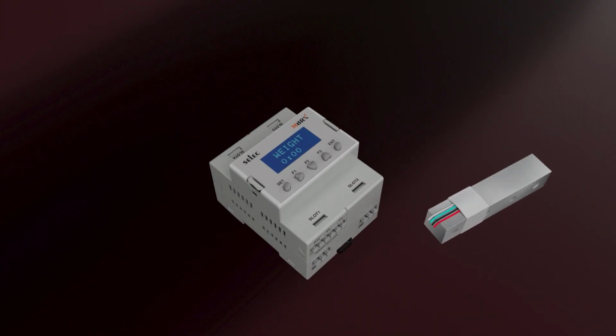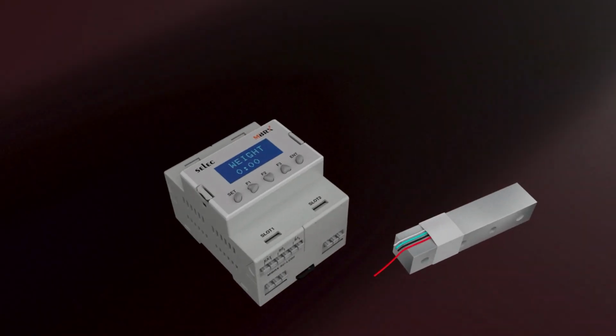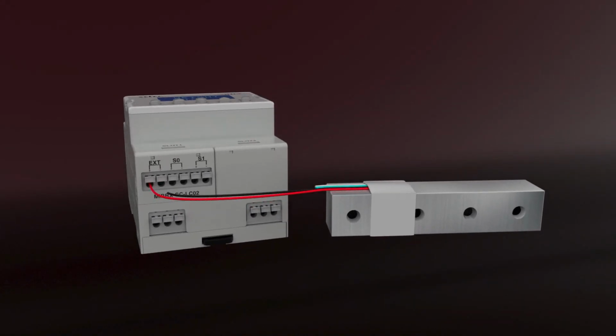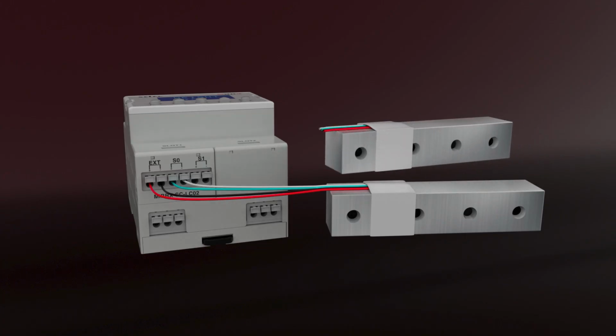The sensor excitation wires are connected to the respective excitation positive and negative terminals, while the sensor signal outputs are connected to the S0 positive and S0 negative terminals. When connecting a second sensor, loop the excitation positive wires of both sensors, and connect them to the excitation positive terminal. Similarly, loop the excitation negative wires, and connect them to the excitation negative terminal. The feedback signal from the second sensor should then be connected to the S1 positive and S1 negative terminals.